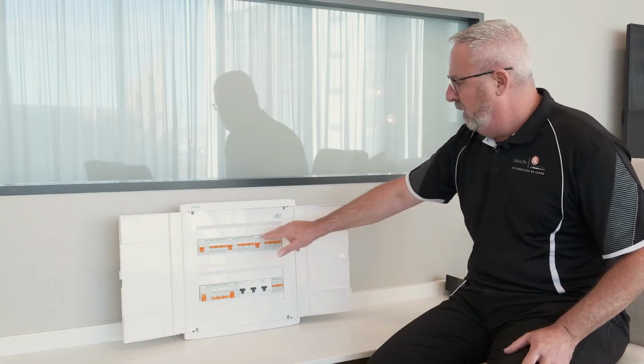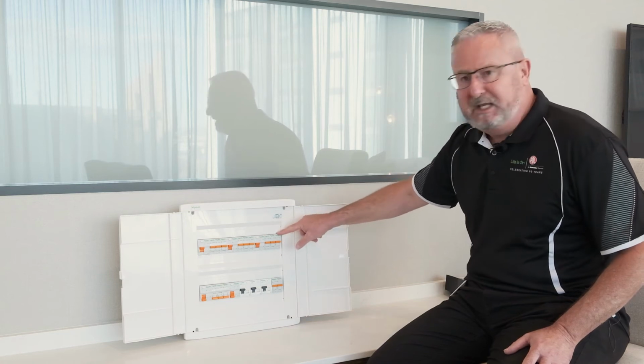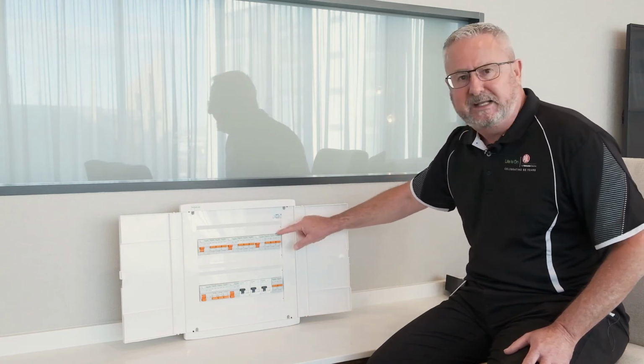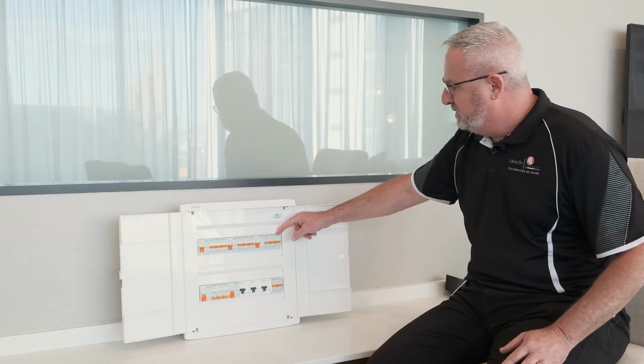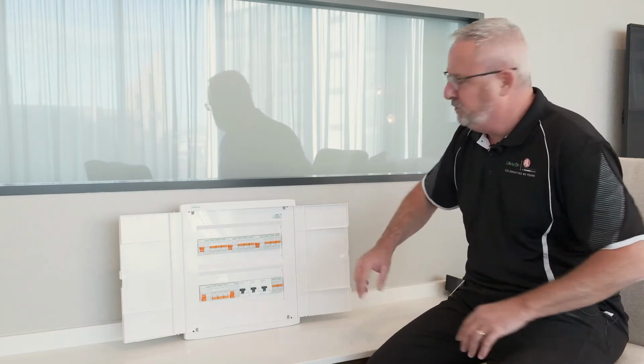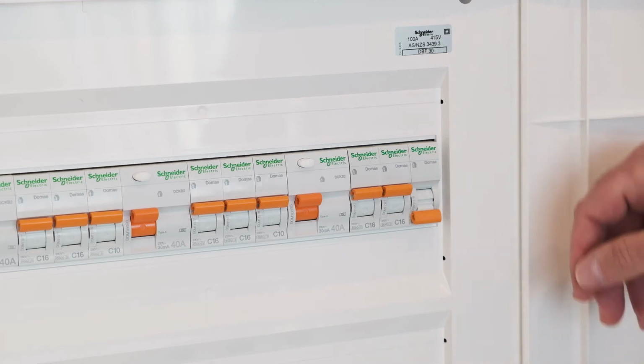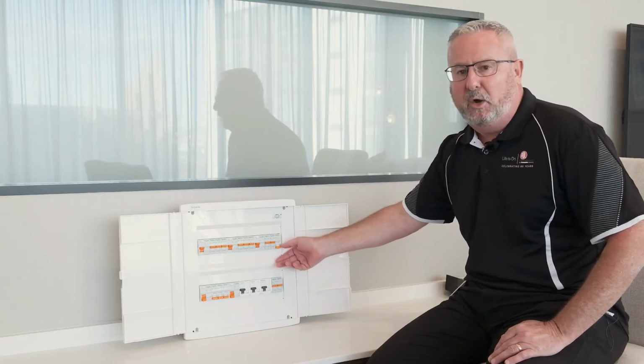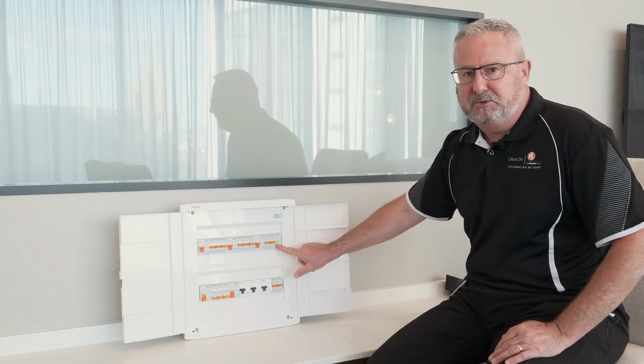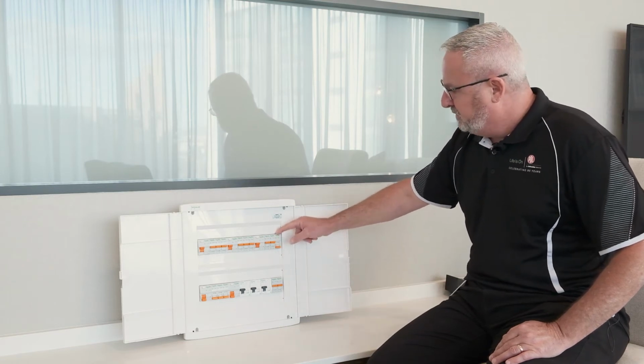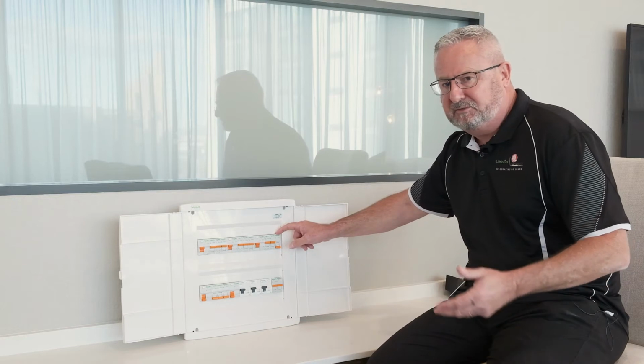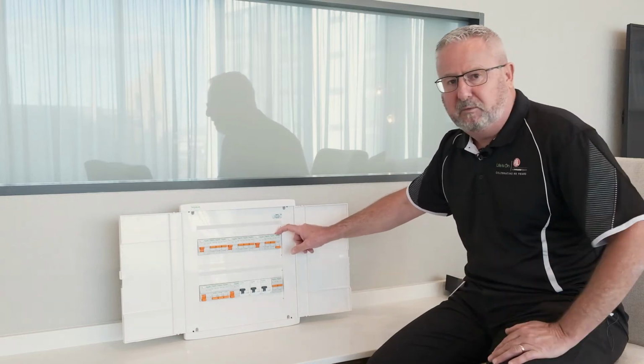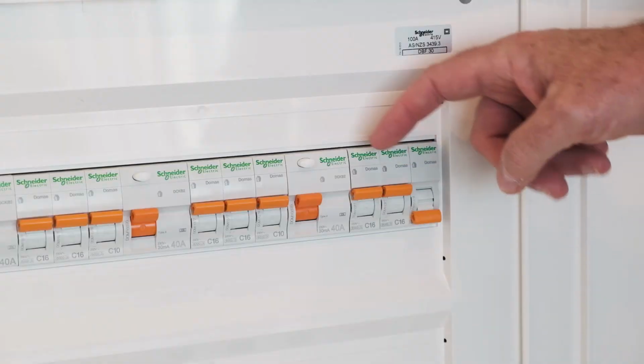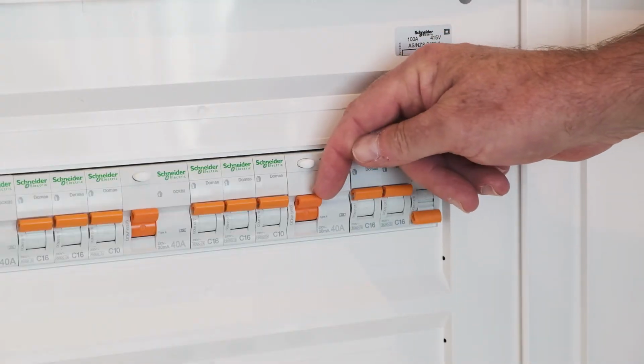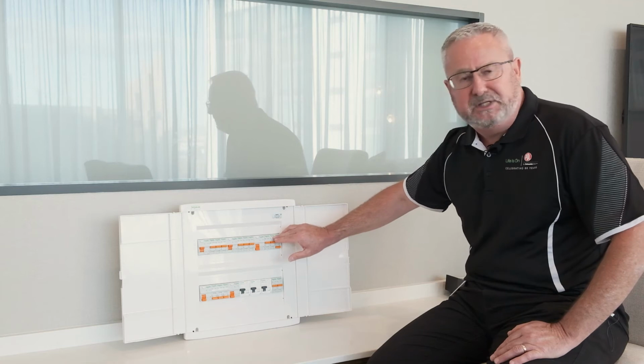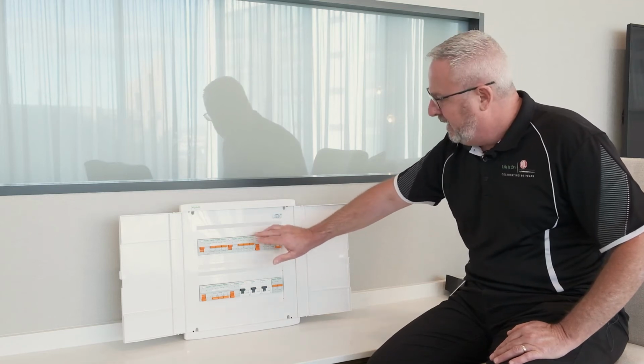The MCB, miniature circuit breaker, protects against overloading. So if I plug in ten toasters all at once and switch them all on, my circuit breaker is going to trip. It detects an overload situation and cuts off that circuit. Now if I had wet hands and touched a power point, there's a potential for electric shock, so the RCD connected to that circuit will trip. So normal protection in a switchboard is overloading and RCD.